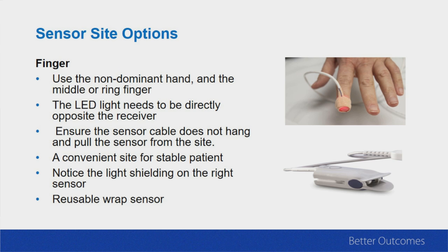Now, if you look at that top sensor on the finger there, that has a Band-Aid wrap on it, the big thing about that type of sensor is you need to make sure that the sending unit, red light, the manufacturer will tell you that's supposed to be on the top of your finger. The sun is supposed to be up, shining down through your finger, just like it's shining down on Earth, and the receiver is supposed to be on the bottom. And you need to line those up directly across from one another.